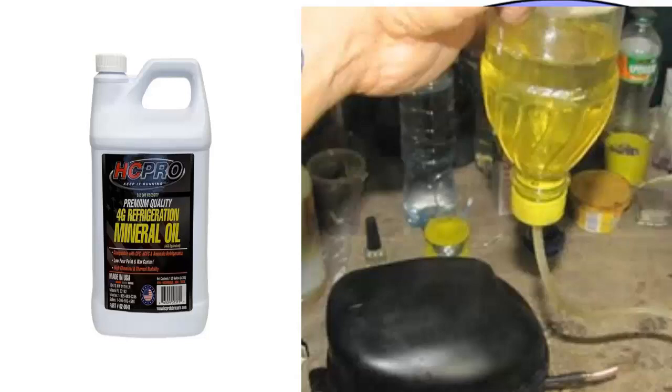Remember to change the compressor oil when the equipment has been exposed to the external environment, for example, due to leaks, that is, totally depressurized, or when the oil presents an abnormal color, such as black or dark brown.